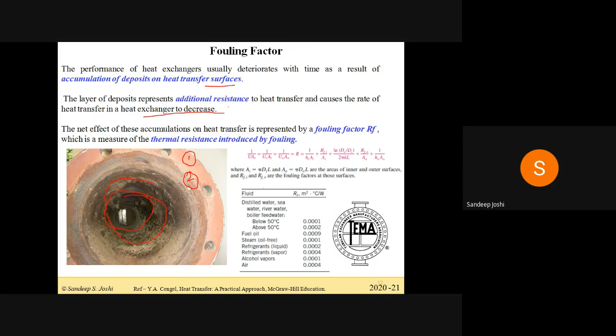See, this is one photograph, which shows a huge pipe of a heat exchanger, where the inside is nothing but scaling, that is the precipitation by water. Okay, the same thing you might have observed in the pipelines of your bathroom, the taps, where after a certain usage of this pipeline, you can see there is a scale formation. So what is the effect of this scale formation? In fact there are two effects. One is an increase in the pumping power requirement, because this will offer resistance to the flow also, and the second is that this scale has low thermal conductivity, and because of that it will offer resistance to the heat transfer.